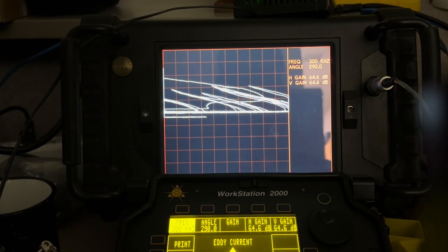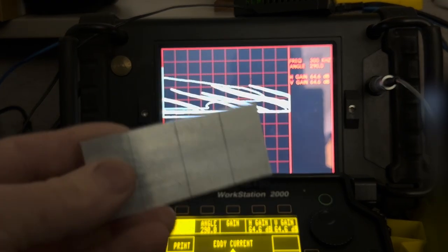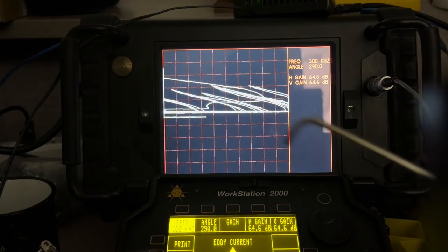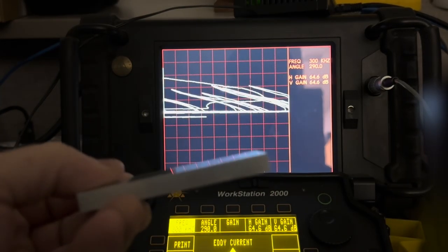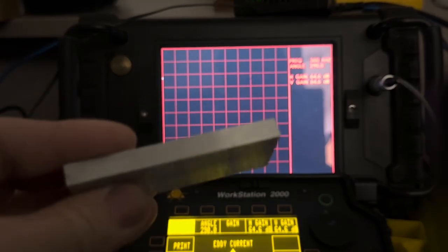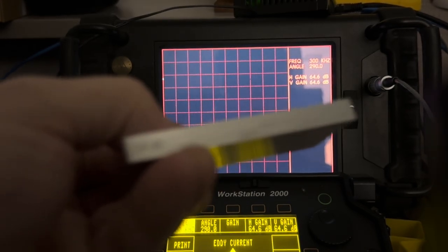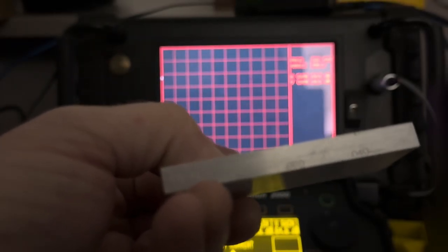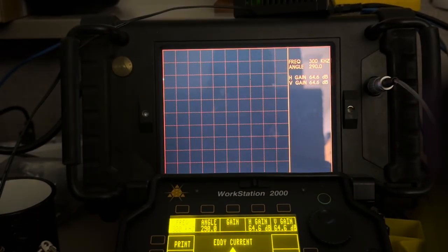In today's video, I'm going to be discussing the importance of proper selection of test frequency when you're doing multi-layer exams. So to start off, I just want to show you a pencil probe scanning an EDM block that's got three different notches. These notches range from 0.2 millimeters deep to a half a millimeter deep, I think. This is in thousandths. So it's 8 thousandths, 20 thousandths, and 40 thousandths. 40 thousandths is pretty close to a millimeter in depth.